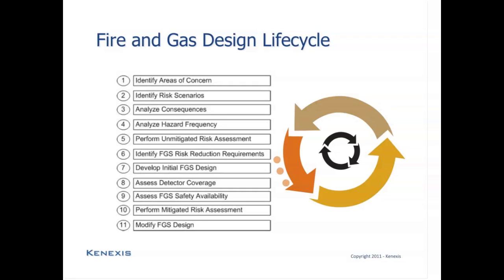You don't want to apply fire and gas systems across the board to every facility. You want to consider the equipment that you're analyzing or the equipment that you have in your facility to determine whether there are any fire and gas detection and suppression concerns. If there are concerns, you're going to want to identify the risk scenarios, which will define what type of detection and suppression equipment you would need.